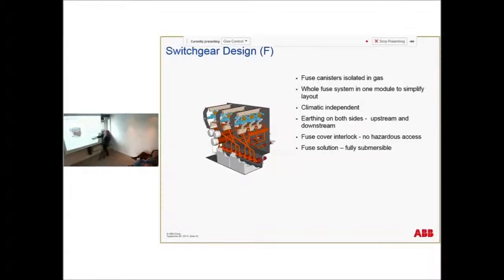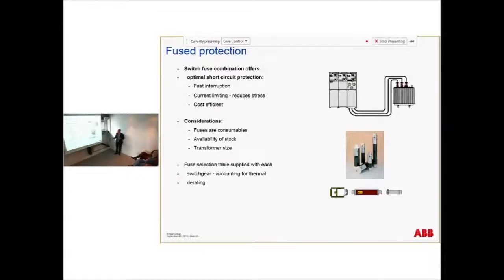And this is when it's with the fuse canisters. Each canister is for a fuse, 442 millimeters. For low voltage, for 12 kilovolt, you have a fuse adapter. So this is put inside this one. Here you see the fuse adapter, which you need to put on, and the striker pin to the front.